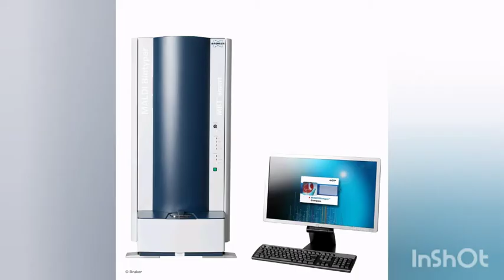MALDI-TOF mass spectrometry, matrix-assisted laser desorption ionization time of flight mass spectrometry, is a commonly used MS technique. MALDI is a soft ionization technique to create ions with minimal fragmentation by using laser energy. In TOF, the protonated ions are accelerated by an electric field to give each ion the same kinetic energy as any other ions. The velocity of the ion depends on the mass to charge ratio, and the time it takes for the ion to reach a detector is measured.